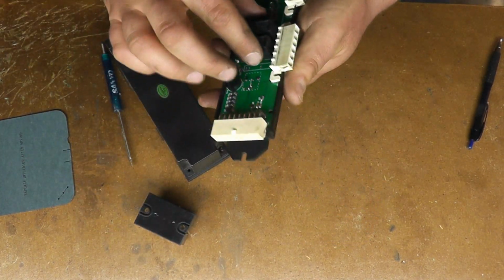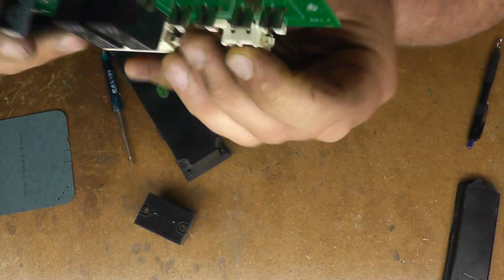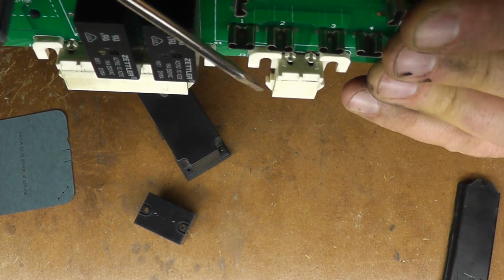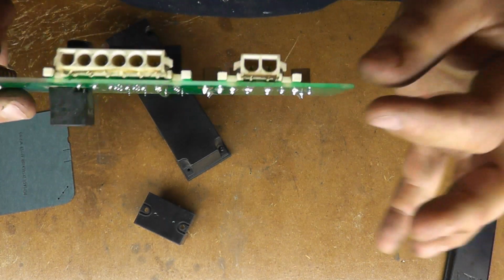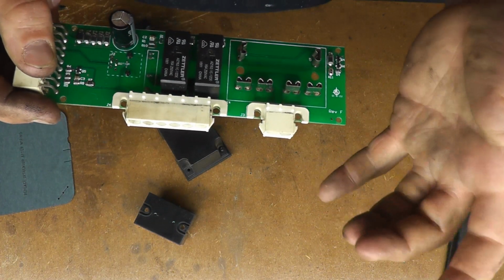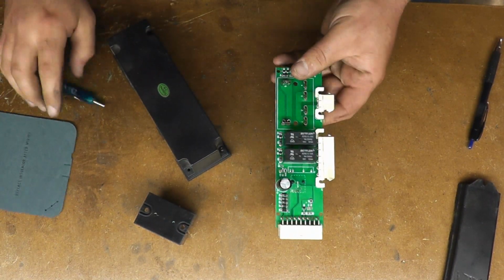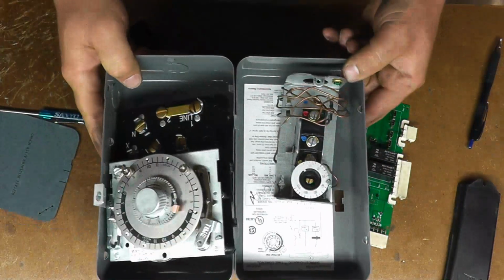And the other thing is, you're pulling all that amperage through basically these two little contact points on the board. So I've actually seen this entire thing melt. It can be completely melted. So I mean, it's just absolutely ridiculous why you would have to go through all solid state stuff to take the place of this.